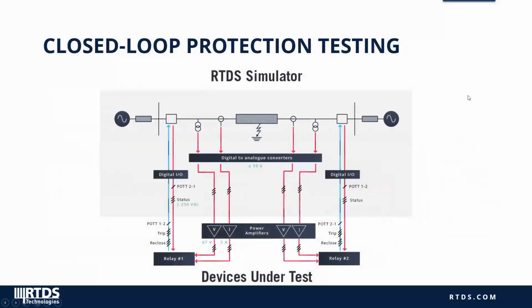So I think it's useful to see how all these things work together to create a hardware-in-the-loop testbed. Here the example is for two relays. So you can see we have a simple simulated system in the box, a transmission line that we can throw a fault on, instrument transformers, breakers, and sources. And we're taking our voltage and currents from the CTs and CVTs, sending it out of the simulation via analog output, then applying those signals to the relay inputs via a power amplifier, which allows us to provide secondary level signals to the relay. And then the relay contacts can actually be wired back into the simulated breaker via digital input. And breaker status can, of course, be sent out via digital output. And this whole interface could also be achieved using IEC 61850.